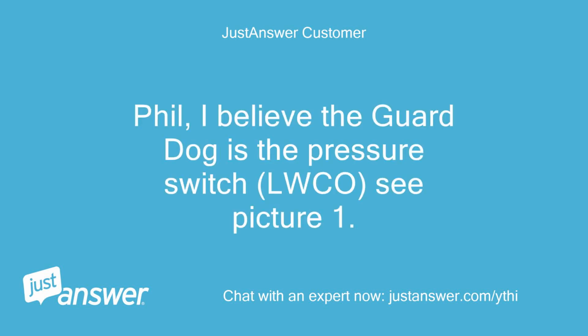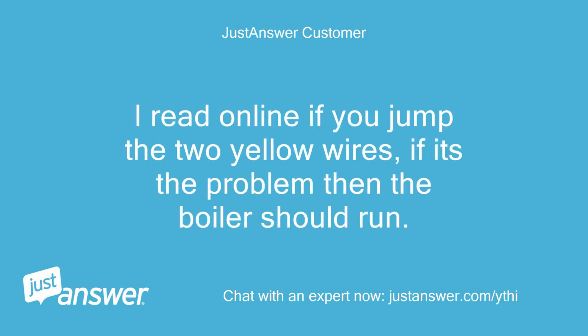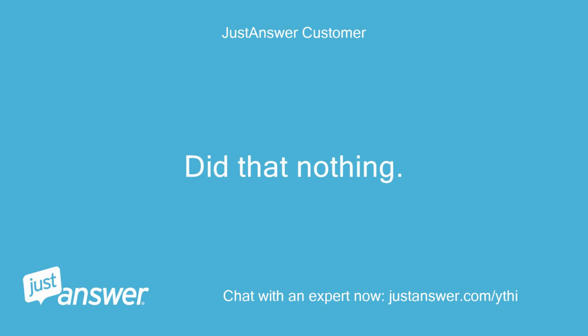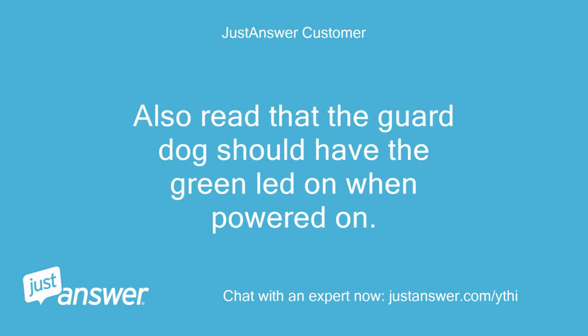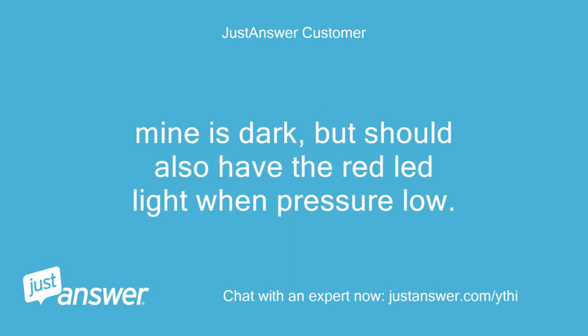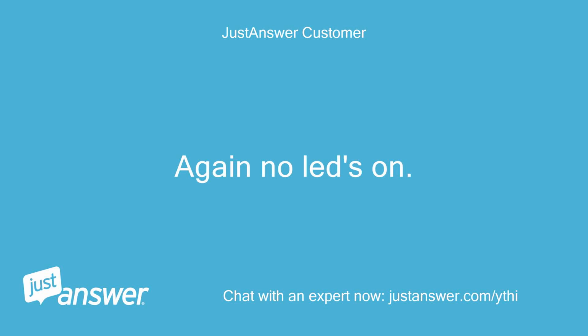Phil, I believe the guard dog is the pressure switch, LWCO, see picture 1. I read online if you jump the 2 yellow wires, if it's the problem then the boiler should run. Did that, nothing. Also read that the guard dog should have the green LED on when powered on. Mine is dark, but should also have the red LED light when pressure low. Again, no LEDs on.